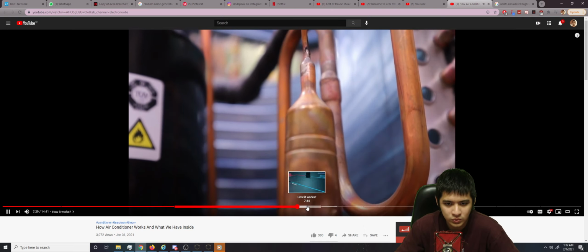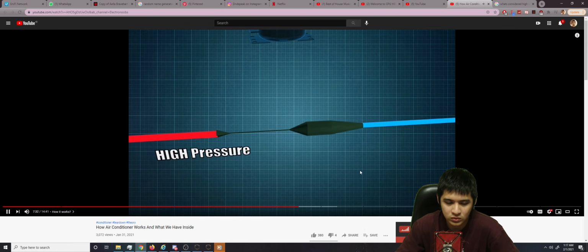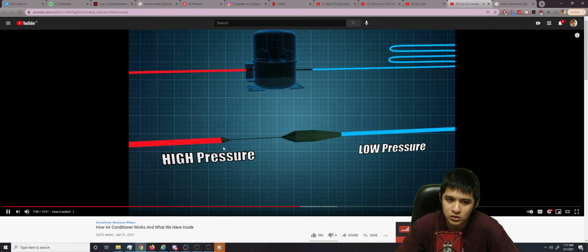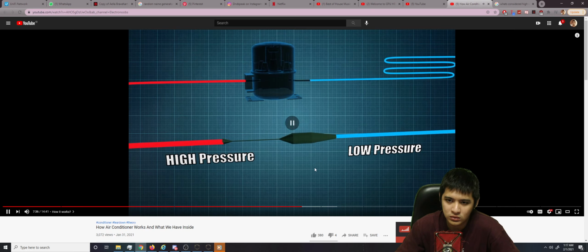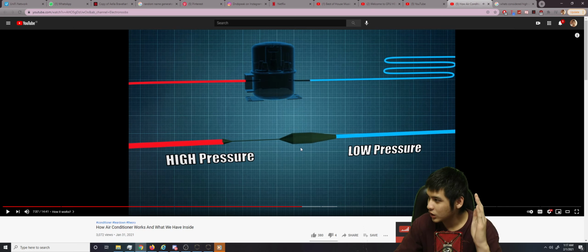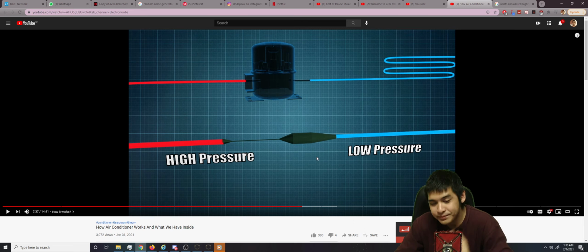Flow. If the flow is restricted, like this we can separate the high pressure on one side and the low pressure on the other side. Okay. The pressure position is actually correct. Just the filter dryer position is incorrect. You don't put a filter dryer or a check valve or whatever it is, depends on manufacturer, on the low pressure side, because that's liquid. I mean, technically both of them are liquid, but I've never seen someone do it this way. It's usually the other way.